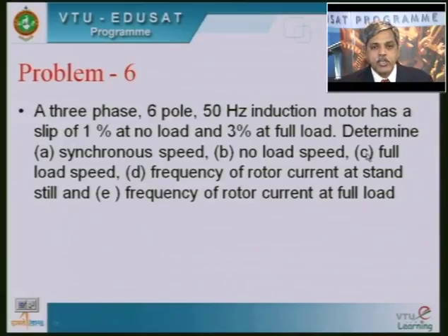There are so many points to calculate here, but these are very simple problems. Now, for this 3-phase induction motor, there are 2 slips given. One is the slip under no load condition, that is 1%, and at full load condition the slip is given to be 3%. Always, the motor under no load condition will be running at a speed very close to the synchronous speed. That is why the slip under no load condition will be smaller compared to the slip under full load condition.